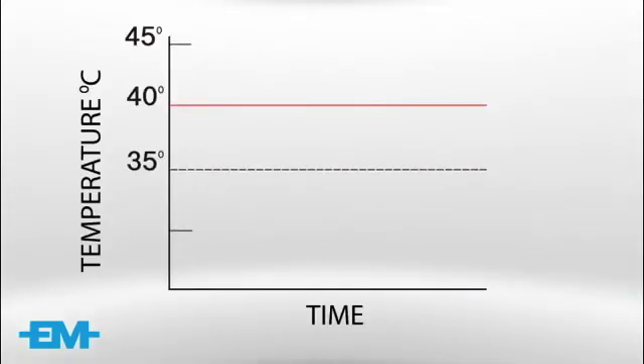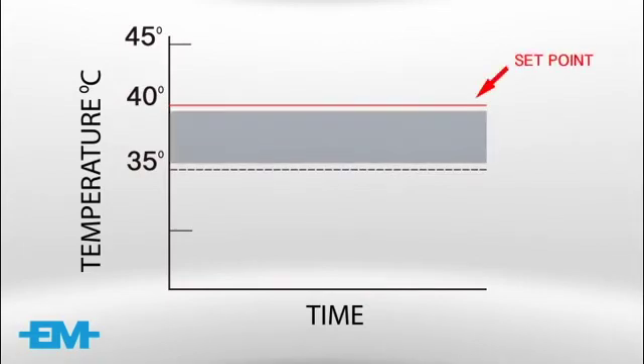Hysteresis is the temperature difference between your set value at which the output will switch off and the value at which it will switch back on again.